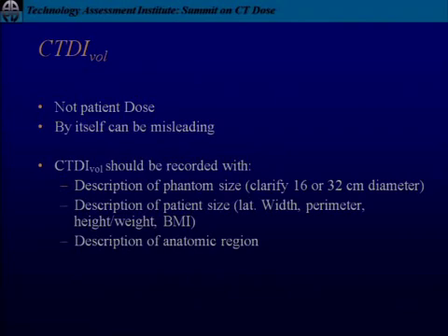We heard about this. Now, I've heard that the IEC has standardized this. It's coming out. Software is going to be rolled out. But I'll tell you, if I walk into my institution right at the moment, I'm pretty sure our peds protocols are going to be given as dose to 32 centimeter phantom. Okay? So please be careful about that. Again, this is our plea for transparency, but you as physicists need to be aware of this, and whoever's doing the protocols need to know what that number on the scanner refers to, right? Because it's going to be a factor of 2 difference in terms of the magnitude of that number on the scanner.